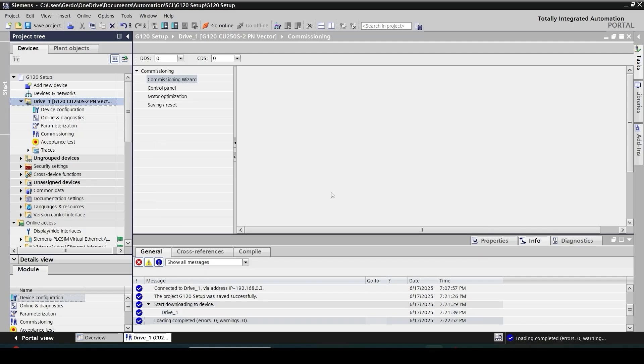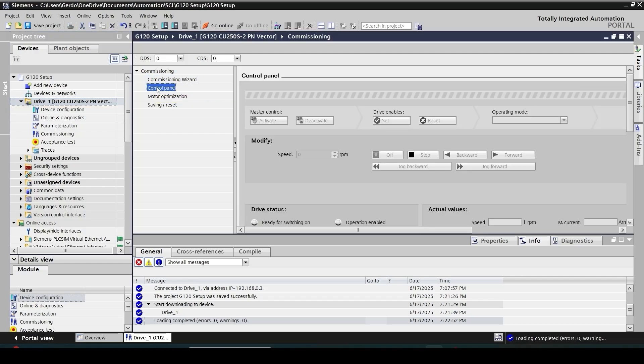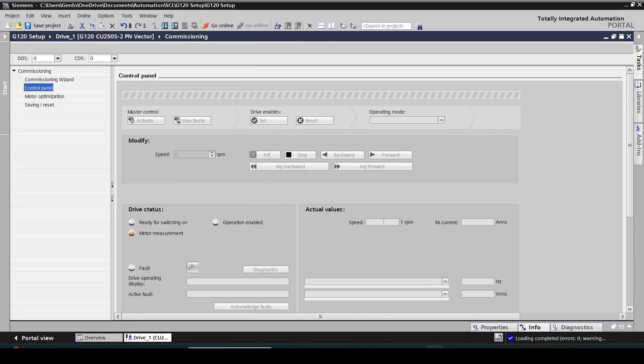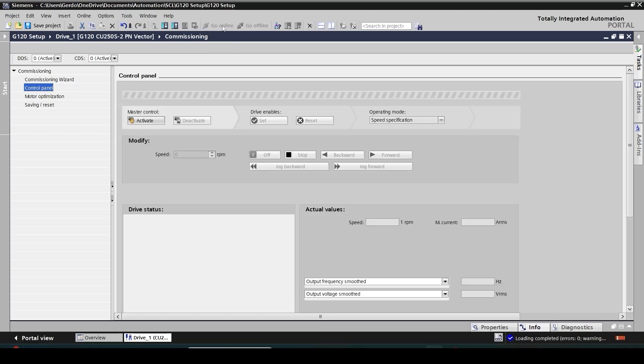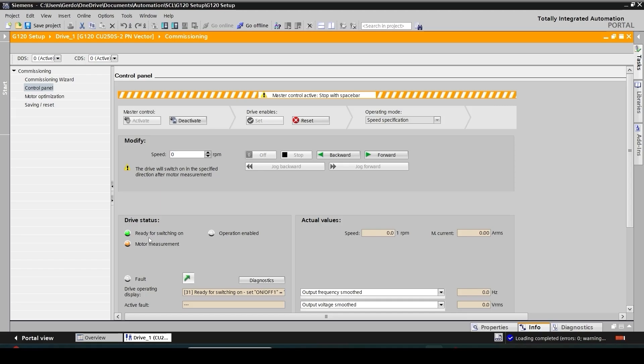Great, everything went well. Now I'm able to check if my drive is able to run my motor. For that I have a control panel here so I'm going to activate this and then just maximize the screen to see the full information. Then go online. I can see that the motor is in measurement mode. No problem. Then click on activate, confirm the master control monitoring time. My drive is ready for switching on.